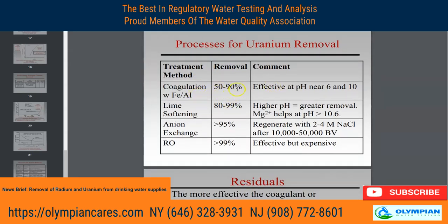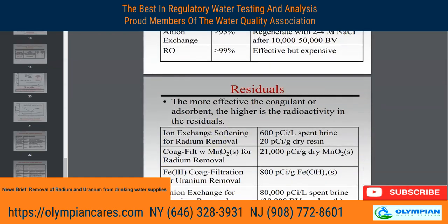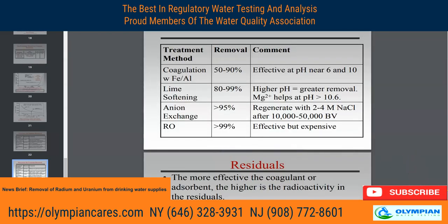How effective are they for removal? You can see 50 to 90% at a pH near 6 and 10, lime softening 80 to 99% or greater removal, and helps at pH 10.6, anion exchange regeneration 2 to 4 M NaCl after 10,000 to 50,000 BV, and RO 99% effective but expensive. And also the residual information here.